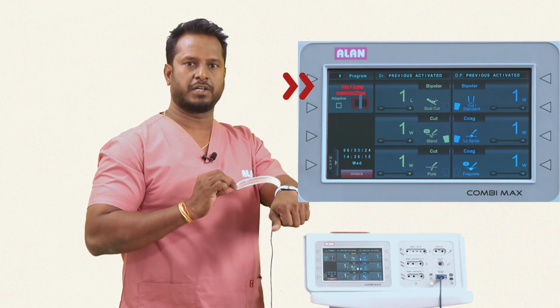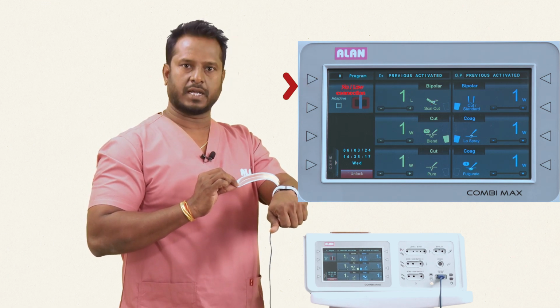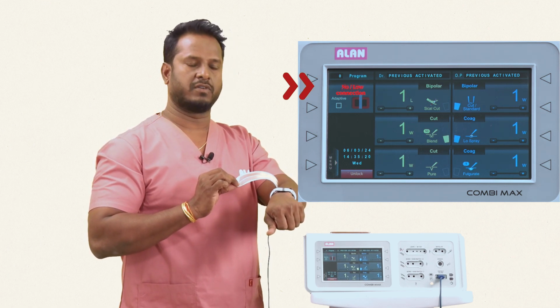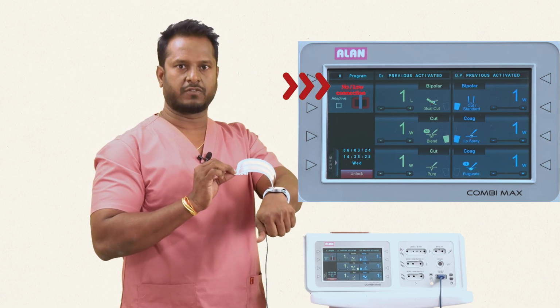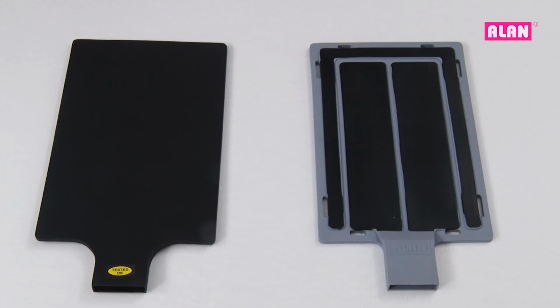the machine has indicated that there is no contact, which means the machine will not deliver any power with this kind of contact. You need to have low, fair, medium or good contact for the machine to deliver the power, which means PPCM is checking the contact quality between you and the return electrode all the time, and it will only deliver the power when the contact is good enough. Patient plates are of two types, split and non-split. Further, they are either disposable in nature or reusable in nature.